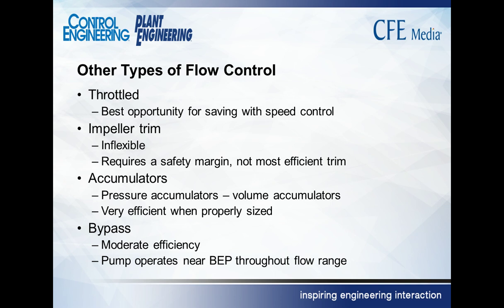Accumulators mean that you can run the pump for a while and then turn it off. If you can cycle a pump on and off, you can have virtually the same savings without having to change the speed of the pump. So systems with accumulators are not good candidates for saving money with variable speed drives. Bypass we haven't talked about. You see bypass on a lot of HVAC systems. With bypass, instead of using a valve to throttle the flow, you simply bypass that flow around a heat exchanger or whatever it is that the flow isn't needed through. So the flow is still being pumped. The advantage is you get to leave the pump operating very close to its best efficiency point. So there are some moderate savings, but not as much as if you can control the flow rather than pump the liquid and bypass it. You're still having to pump the liquid.